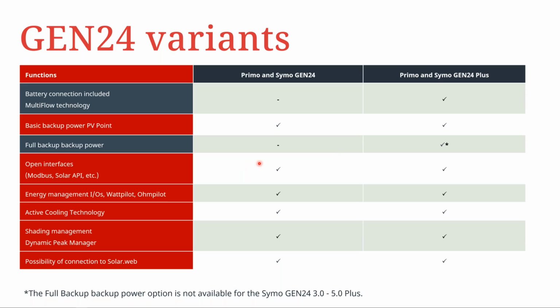are available on both variants of the GEN24 series, as well as your energy management. So this is using excess PV surplus energy to trigger different relays to open with the IOs, or utilizing the Wattpilot and Ohm Pilot. This is available on both GEN24 and GEN24 Plus. Both inverters use the same active cooling technology, as well as our shade management, or dynamic peak manager. And lastly, the possibility of connection to SolarWeb is available on both versions of the inverter.